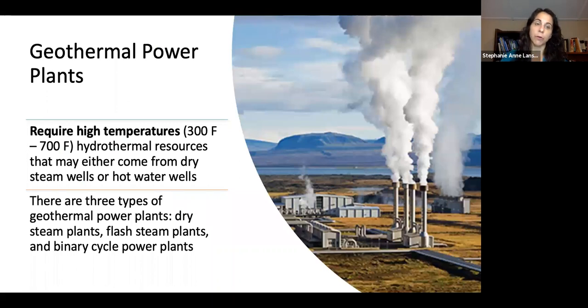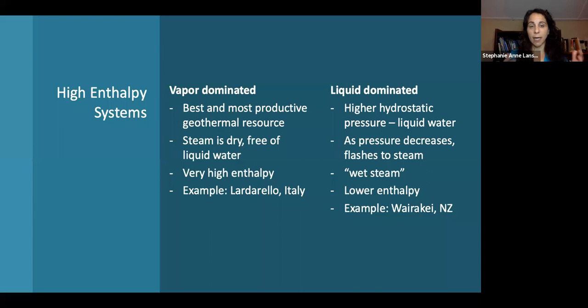Geothermal power plants producing electricity require high temperatures from 300 to 700 degrees Fahrenheit from dry steams or hot water wells. We have dry steam plants, flash plants, and binary cycle plants. High enthalpy vapor-dominated systems with dry steam free of liquid water are most productive. Liquid-dominated systems have higher hydrostatic pressure, and as pressure decreases, they flash to steam. This wet steam drives the turbine.